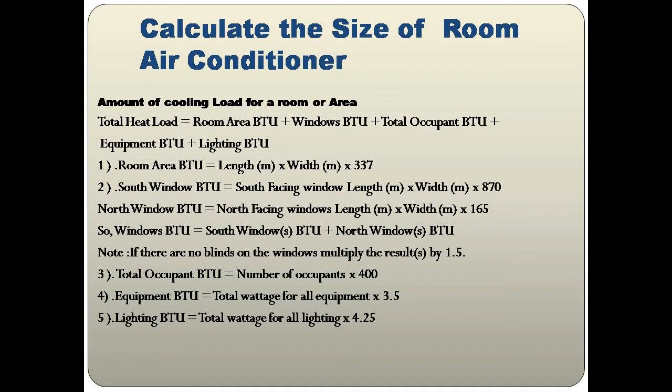For Total Occupants BTU: number of occupants × 400, since each person is considered to emit 400 BTU of heat. For Equipment BTU: total wattage of all equipment × 3.5. For example, one computer normally uses 120 watts; multiplying by 3.5 gives the equipment BTU.